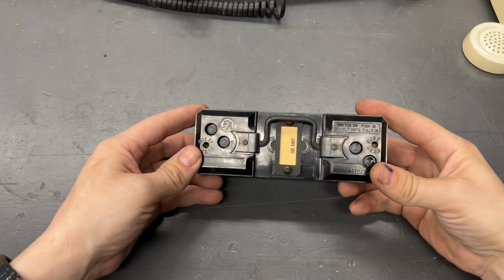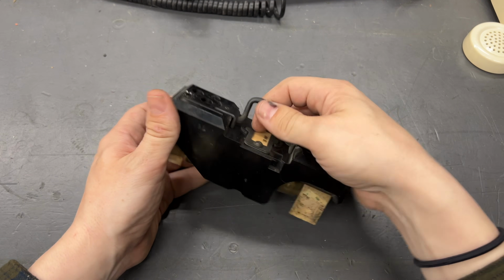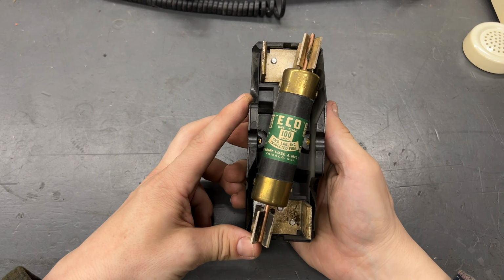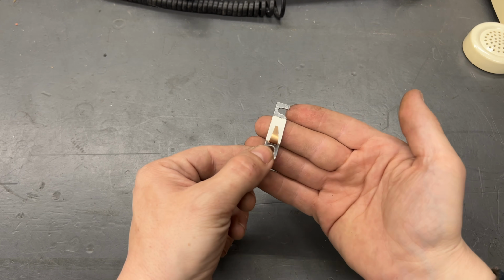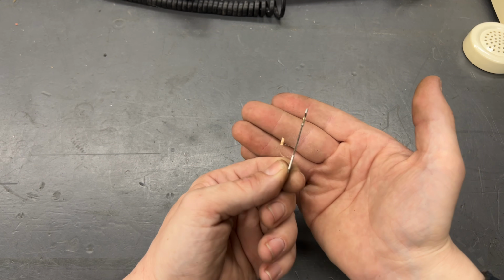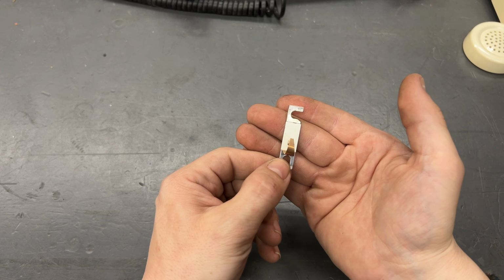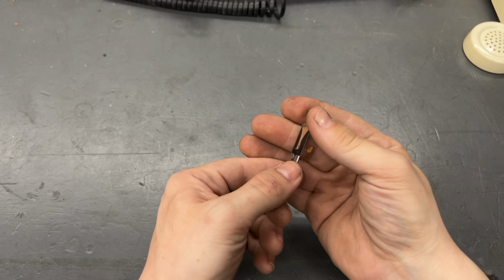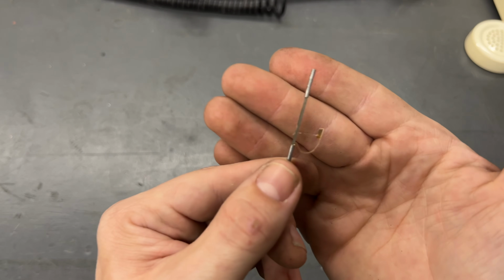At the end of each aisle of equipment is one of these. This is called a safety fuse, and it's the master fuse for the entire aisle, usually rated at 100 amps. Each frame in the aisle then has its own 20 amp fuse, sometimes more than one if the frame needs more power than that. Finally, each individual circuit is protected by a grasshopper fuse, usually rated at 1 1/3 amps. These are the ones that blow most frequently, and when that happens, it's usually my fault.